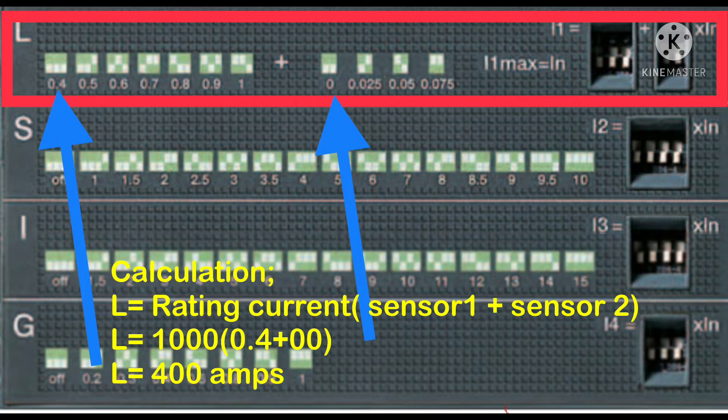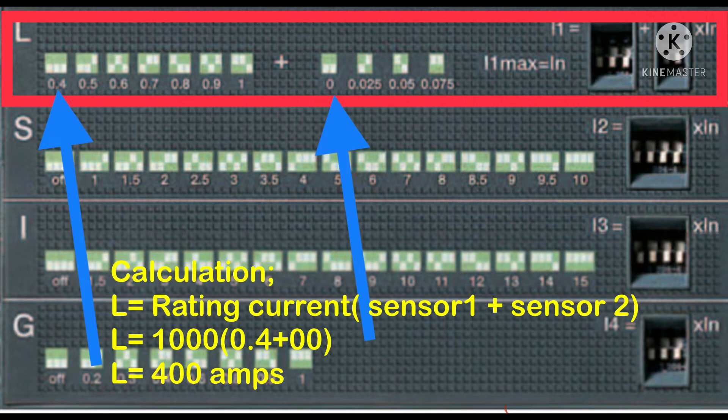current multiplied by (sensor 1 plus sensor 2). That means our rating current is 1000, and if you add sensor 1 and sensor 2, the value is 0.4. Multiply 0.4 by 1000 amperes, and the result is 400 amperes.